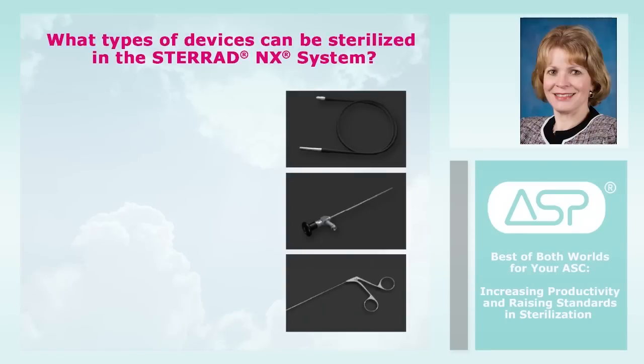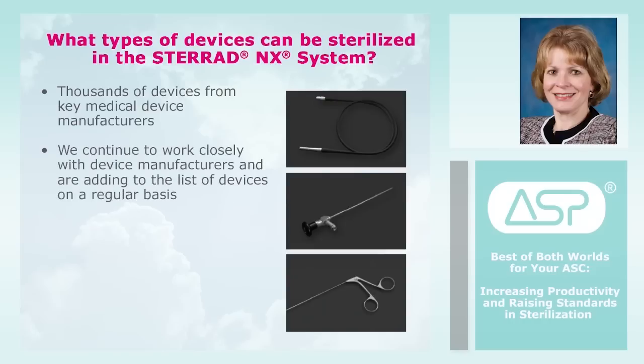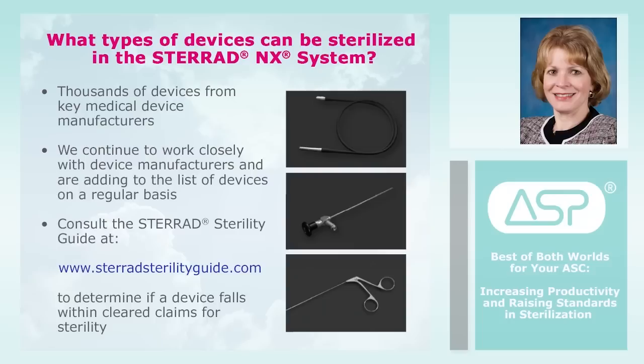The STERRAD Systems brand has the most IFU endorsements from medical device manufacturers for low-temperature sterilization. Thousands of devices commonly used in ASCs from key medical device manufacturers can be processed in the STERRAD NX system. Olympus, Karl Storz, Richard Wolf, and Gyrus ACMI have all announced certain flexible endoscopes that can be processed in the STERRAD NX system. We continue to work closely with device manufacturers and are adding to the list of devices on a regular basis. For example, ConMed, Linvatec rigid telescopes, Stryker camera heads, and many more have been recently added to the list of devices that can be sterilized in the STERRAD system.